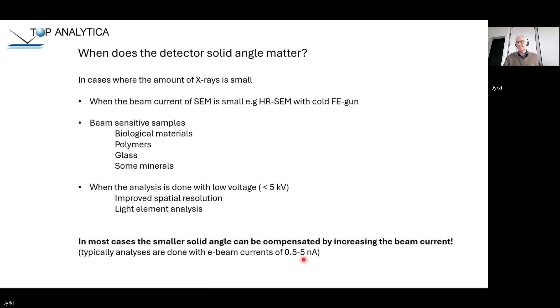I was telling that glass can be a challenging, beam sensitive sample. This is an example where we have done a repeated measurement on a glass. Beam current was really low, dead time only 3%, 3 kV voltage, and 1 hour measurement time per spectrum, because I was interested in the trace element analysis of this glass. But the analysis is also from a relatively big area. It was not a spot. If we use a spot analysis, it is even more damaging for the sample.